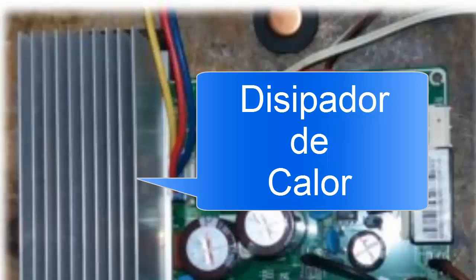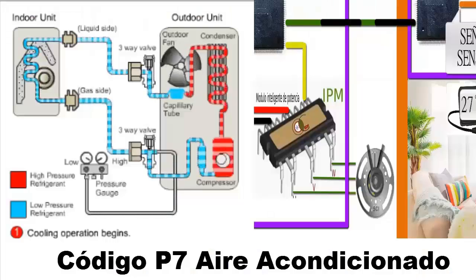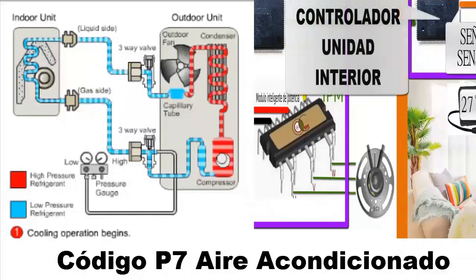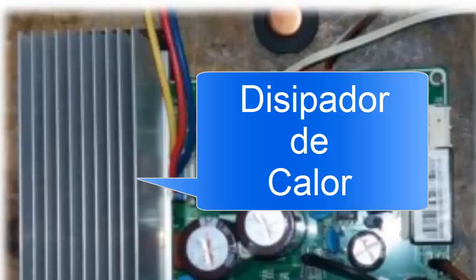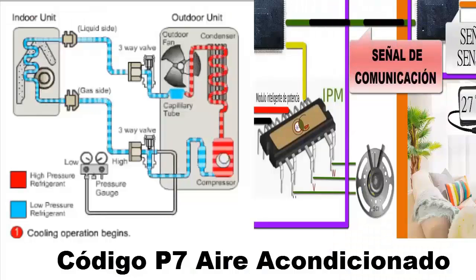The first step to solving this problem is to physically inspect the electronic card to verify that the aluminum heat sink is firmly in contact with the IPM. It is crucial to de-energize the equipment before performing this test and wait for the necessary time for capacitor discharge.